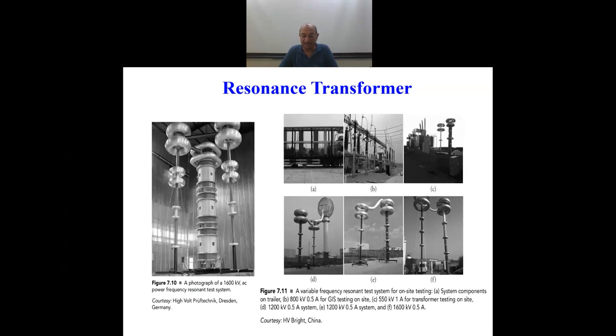So as you see in this diagram, in A, system components on a trailer. B is 800 kV, 0.5 ampere for GIS testing on site. This is GIS testing going on site with the help of a tuned frequency AC power frequency test transformer. In C, as you can see, a 550 kV, 1 ampere set for transformer testing on site. This is transformer testing going on after the installation of the transformer at the site.